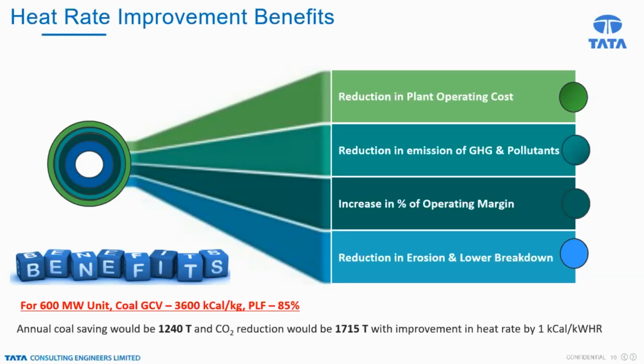And to give just an example of the importance of heat rate, take every 1 kilocalorie per kilowatt hour improvement for a unit size of 600 megawatts subcritical, considering the specified coal GCV and PLF. That 1 kilocalorie improvement will give an annual coal saving of 1,240 tons, which means a CO2 reduction to the tune of 1,700 tons per annum. We may think that 1 is too small a value, but for a plant of 600 megawatts, the annual coal saving is 1,200 plus tons. So definitely it will save operating cost, give a better operating margin, and lower emissions. This is one typical example.